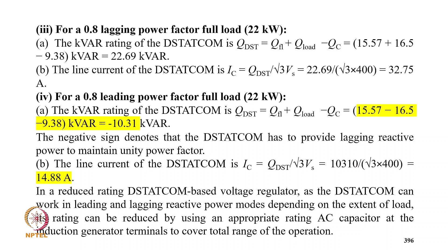So in the induction-generator-based system, the DSTATCOM can work in leading and lagging reactive power mode depending upon the load. The DSTATCOM rating can be reduced by using an appropriate AC capacitor at the induction generator terminal to cover the total range of operation. In most cases, half the required rating other than no load can be selected as the rating of the STATCOM, and the full load reactive power rating is selected as the rating of the AC capacitor. At no load the STATCOM works as an inductor, and at full load it works as a capacitor.